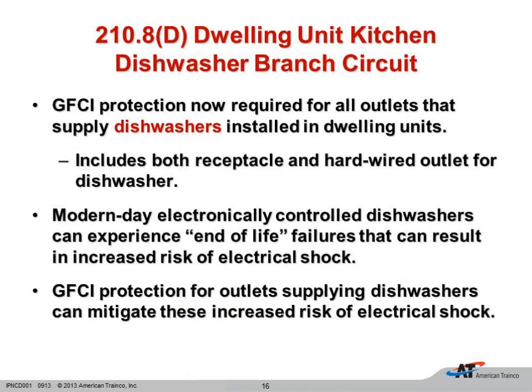Also, in Part D of this, the dishwasher now has to be on GFCIs, and that doesn't matter where the dishwasher is located. It can be 20 feet away from the kitchen sink. Wherever you put the dishwasher, it is going to have to be GFCI protected. It doesn't matter if you hardwire the dishwasher or put it on a cord and plug like I like doing. We can see that these dishwashers do have an end of life, and when they do fail, there is an increased risk of shock, so GFCIs should become very important.